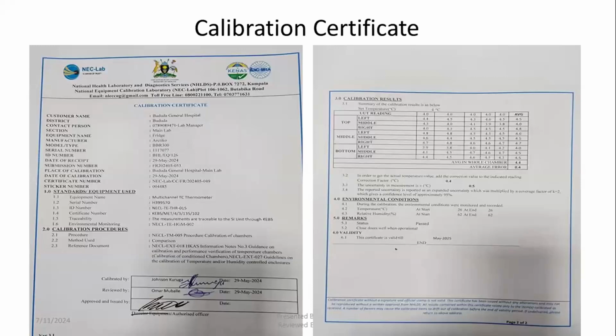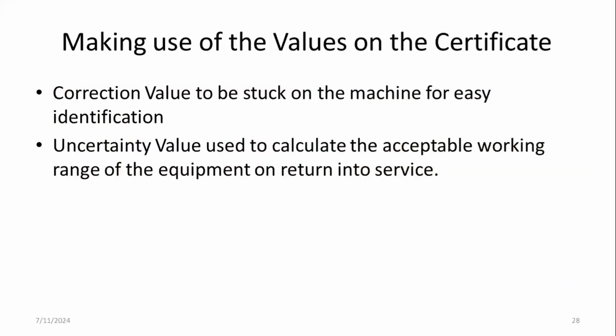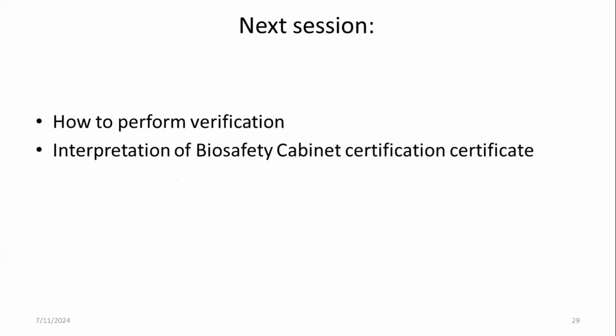That is just a sample of the certificate, and all those that I've talked about are all stipulated in this certificate. So to make use of these values, once you identify a correction value, this value must be stuck onto the machine for ease of identification, and then the uncertainty value is used to calculate the acceptable working range of the equipment on return into service.